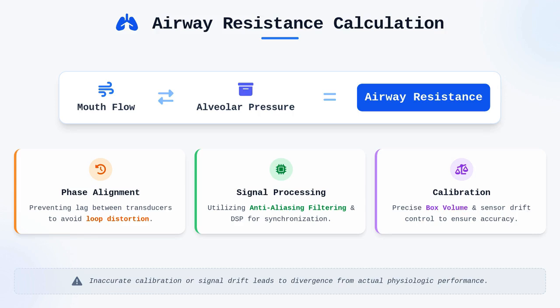Engineers use anti-aliasing filtering and digital signal processing to ensure that the timing of these signals remains perfectly synchronized, even at high respiratory frequencies. These systems must also account for the inherent box volume constraints, as the total volume of the chamber influences the magnitude of the pressure swing generated by the patient. If the volume of the box is not precisely calibrated, or if the electrical sensors show signs of drift, the calculated resistance values will diverge from actual physiologic performance.